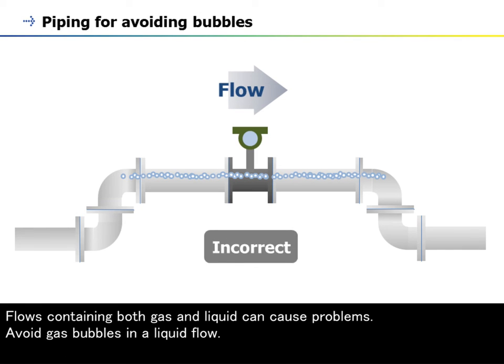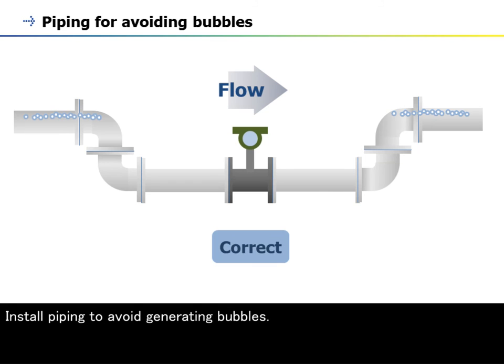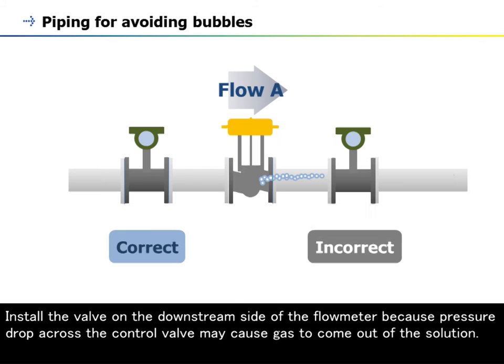Flows containing both gas and liquid can cause problems. Avoid gas bubbles in a liquid flow. Install piping to avoid generating bubbles. Install the valve on the downstream side of the flow meter, because pressure drop across the control valve may cause gas to come out of the solution.